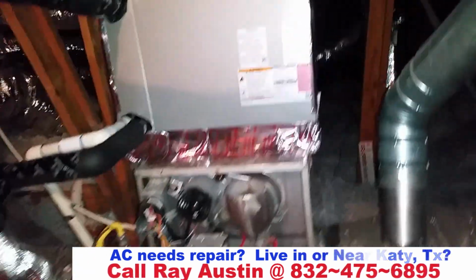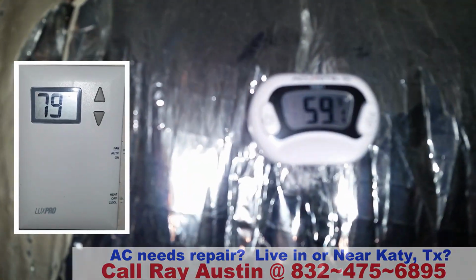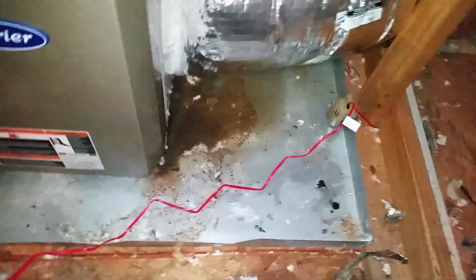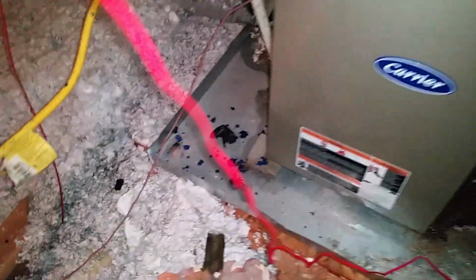What we try to shoot for in the Texas area is anywhere between 15 to 20 degree temperature drop. Here you can see 20-degree drop, which is a good indication. Anytime I hit the upper end of that range, it's a good indication that everything is working well. If it's down around 15 degrees, I tend to have hesitancy because 9 times out of 10 it'll be calling me back when it's really, really hot if the system can't keep up.